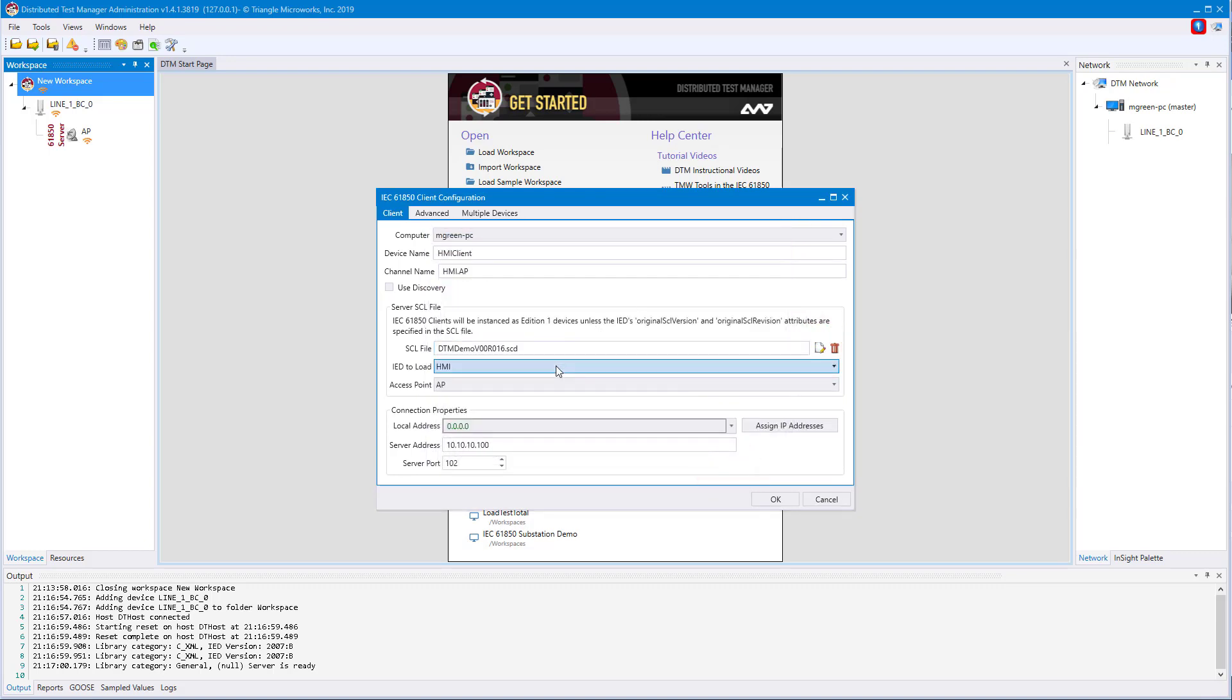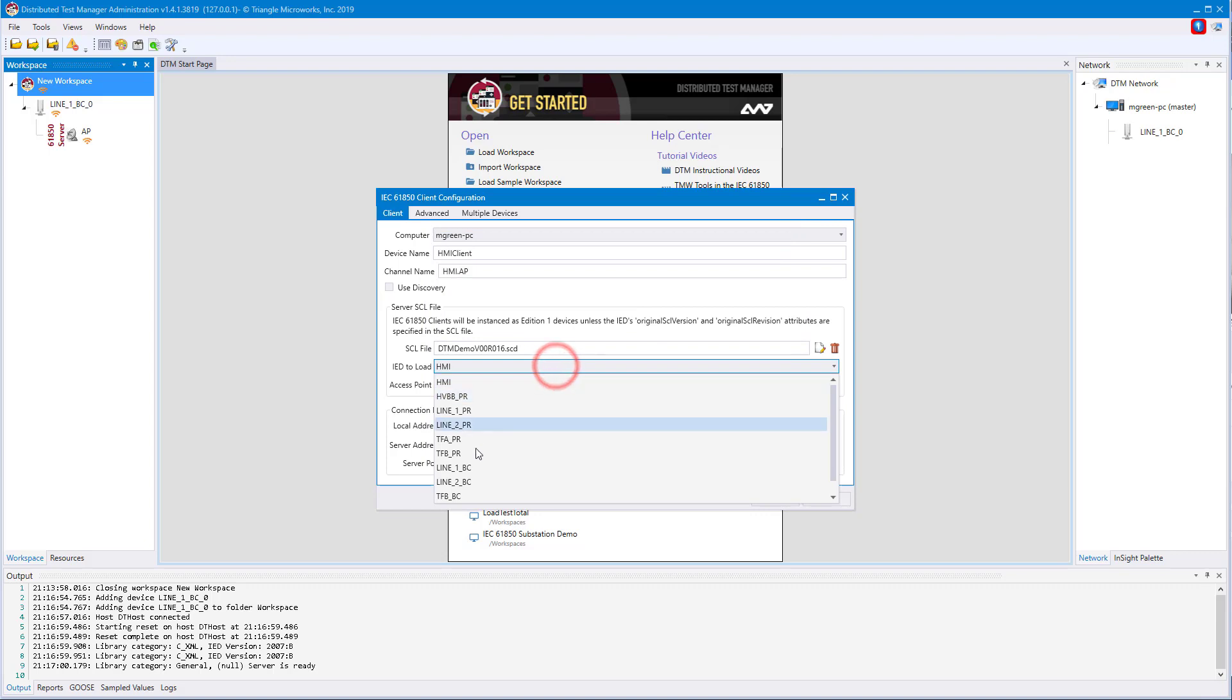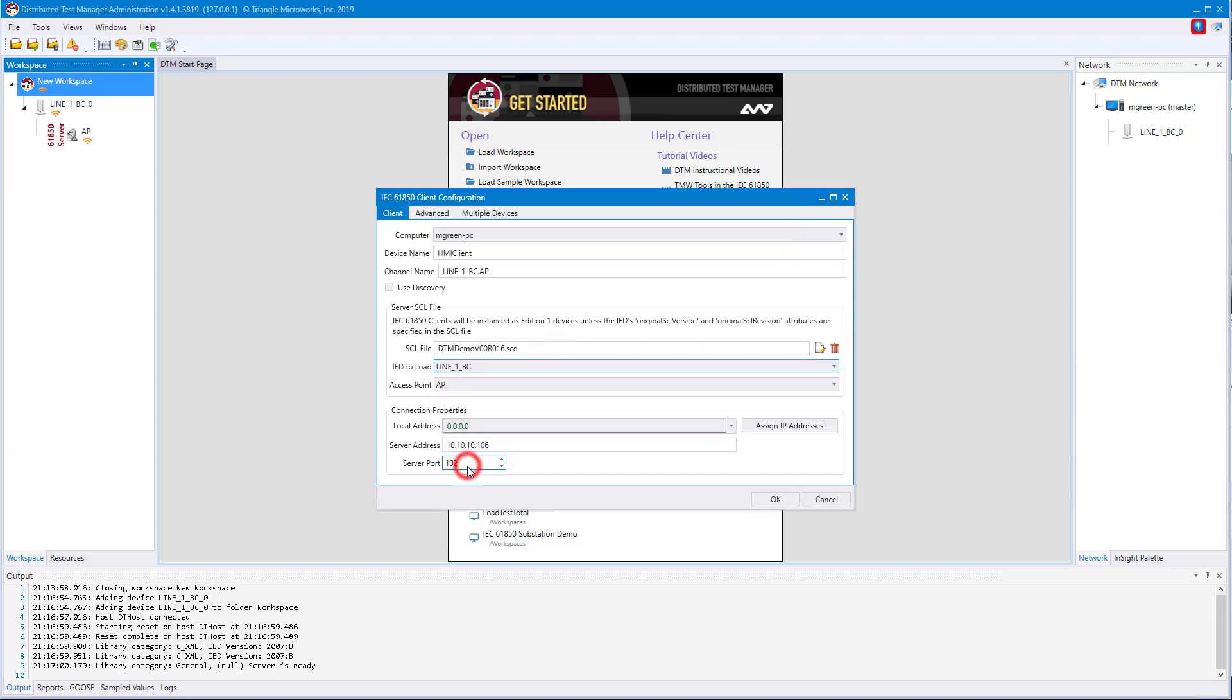Again, we'll need to select the proper IED to load and give it the right IP address. If you did not have the SCL file to configure your client, you could always click use discovery and the IEC 61850 client would discover the model based on the server's configuration.